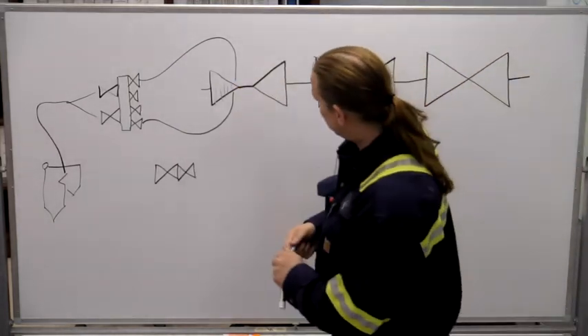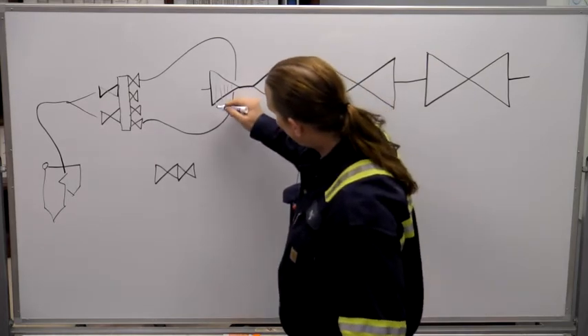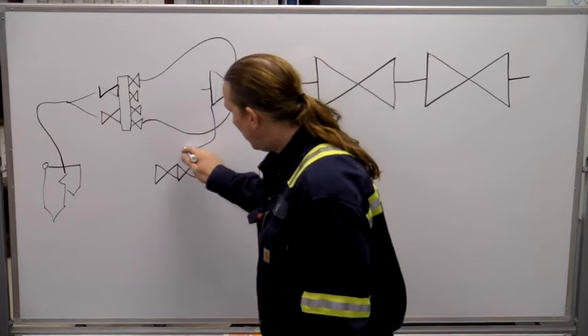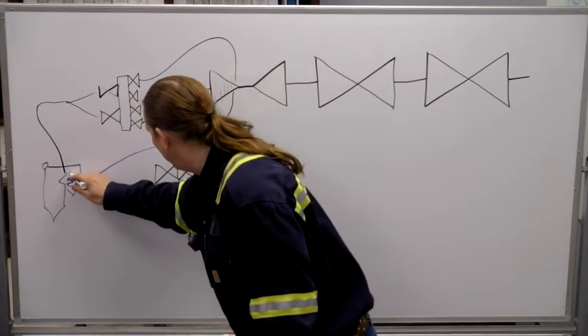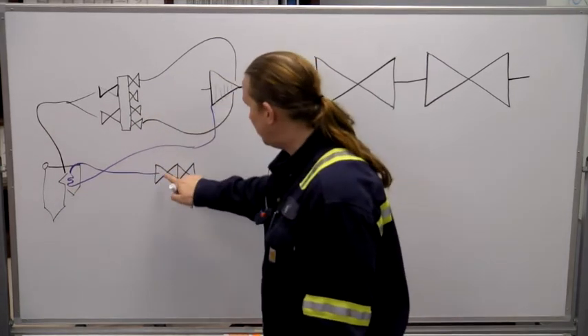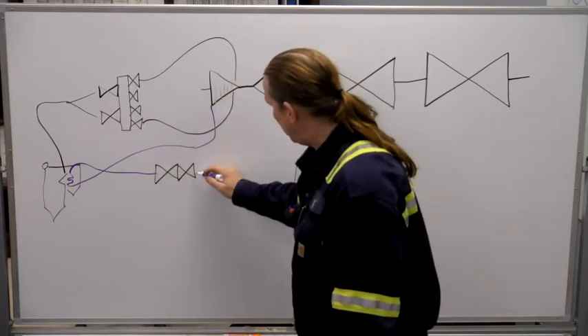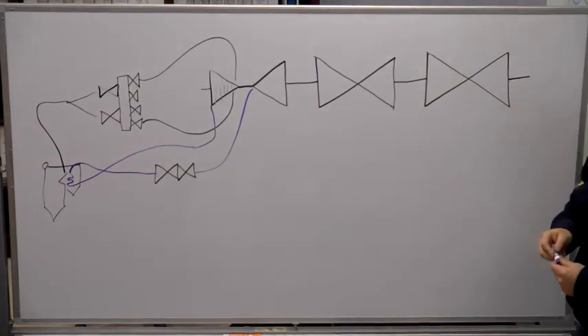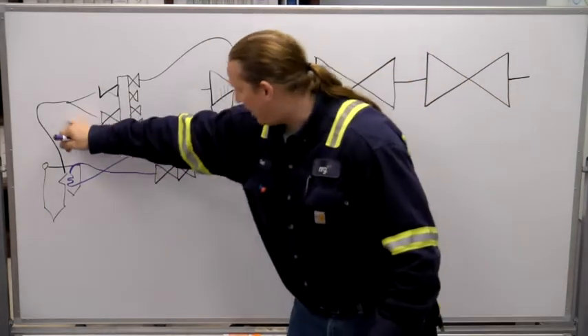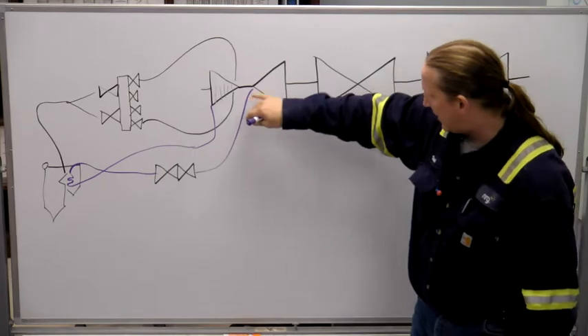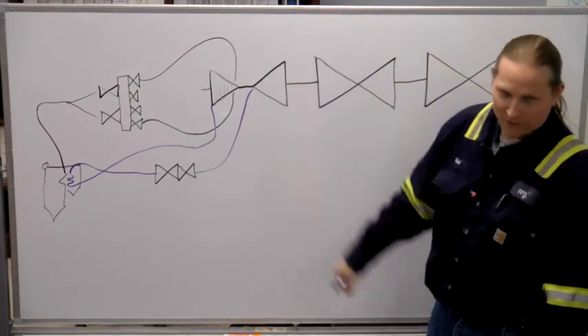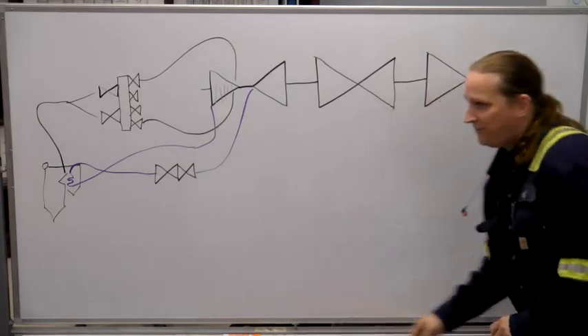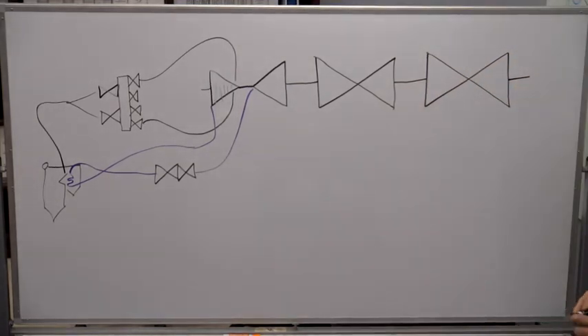The steam exhausts from the HP turbine, goes into the back pass and gets heated back up, and then goes to the intercept valves before it goes into the IP turbine. IP is intermediate pressure. We started out at about 2,500 pounds, and now we're at like 600–700 pounds somewhere in there.